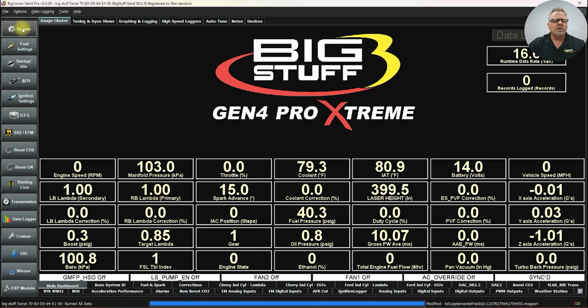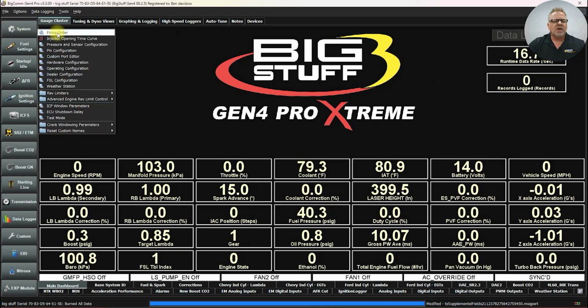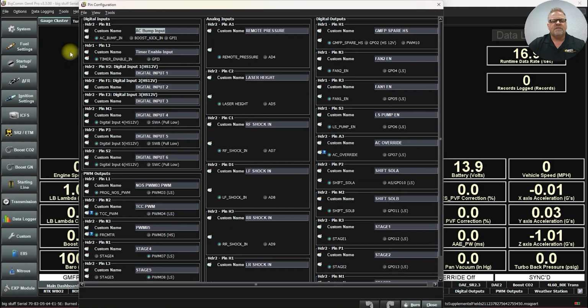We've also freed up a couple of our inputs for use. If I come over to System and go to Pin Configuration, before there was a value here called Remote Accelerometer. We've made this available now — the Remote Accelerometer verbiage is gone, and we've changed this input so it's available to be used as any 0 to 5 volt DC input.